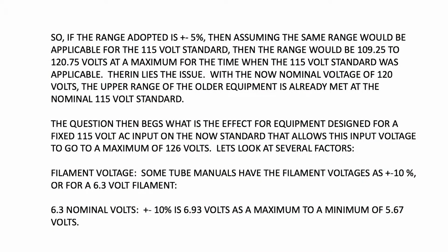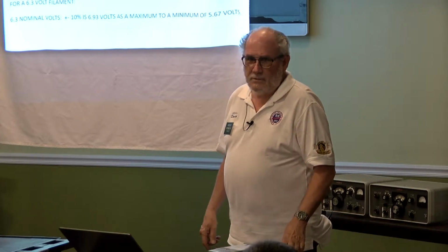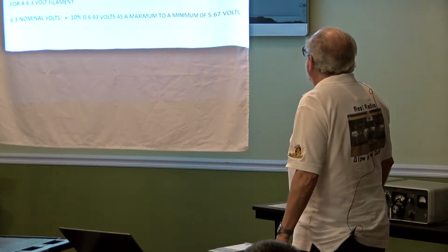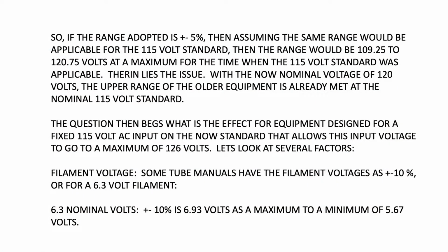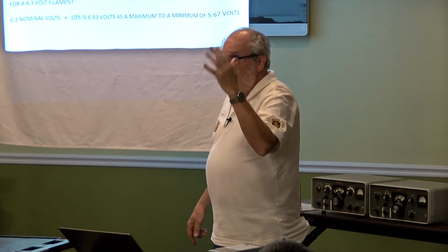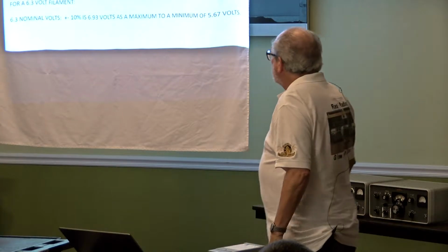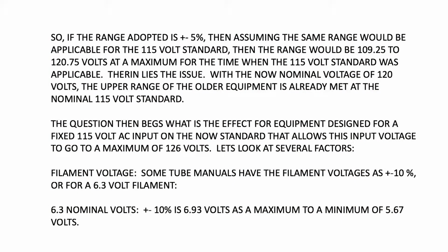So if the range is plus or minus 5%, then assuming the same range would be applicable for the 115 volt standard, the range would be 109 to 121 volts at maximum for the time when the 115 volt standard was applicable. Therein lies the issue. With the now nominal voltage of 120 volts, go home and measure it. I bet you don't have 120 volts. That's right. The upper range of the older equipment is already met at the 115 volt standard. So if the 115 volt standard's upper limit was 121 volts, and Nick has 127 volts, what's happening to his equipment? The question then begs, what's the effect for a fixed 115 volt AC input on the now standard that allows this voltage to go to a maximum of 126 volts?